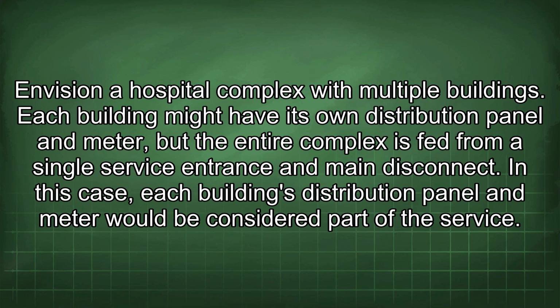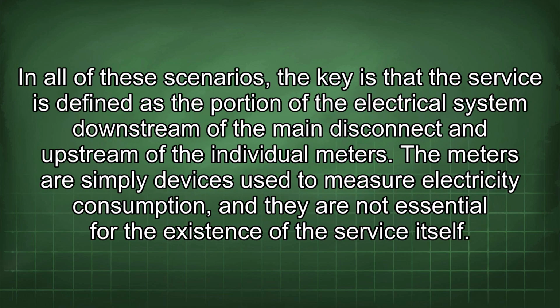Envision a hospital complex with multiple buildings. Each building might have its own distribution panel and meter, but the entire complex is fed from a single service entrance and main disconnect. In this case, each building's distribution panel and meter would be considered part of the service. In all of these scenarios, the key is that the service is defined as the portion of the electrical system downstream of the main disconnect and upstream of the individual meters.